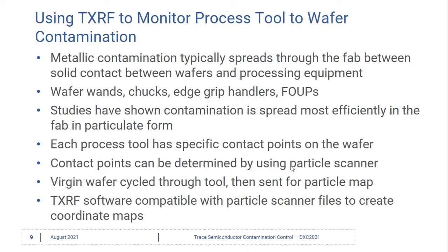We can determine what these contact points are by using another type of equipment called a particle scanner. We'll take a virgin wafer, cycle it through the processing tool, and then send it for a particle map.